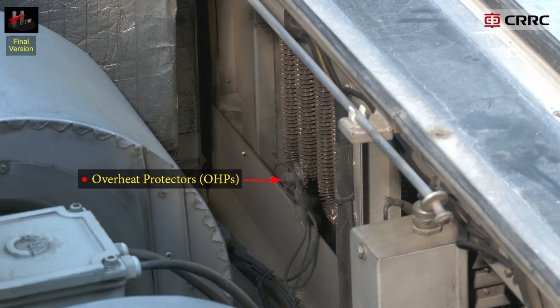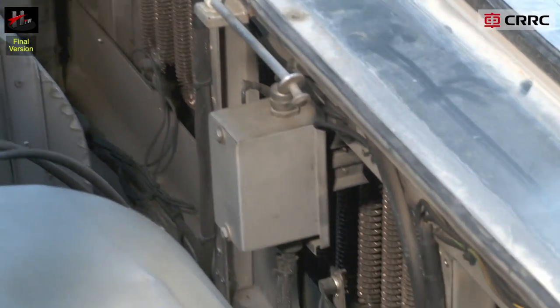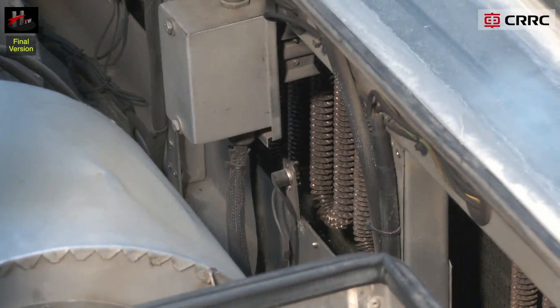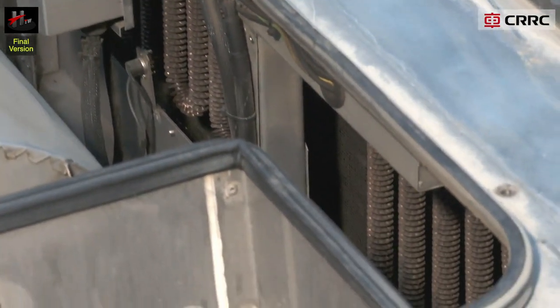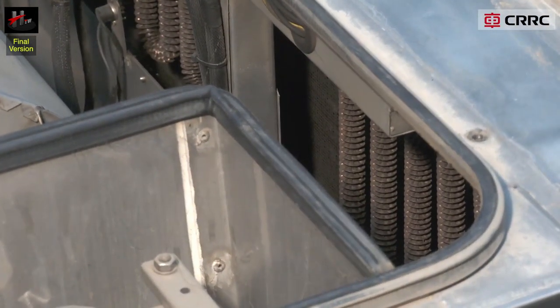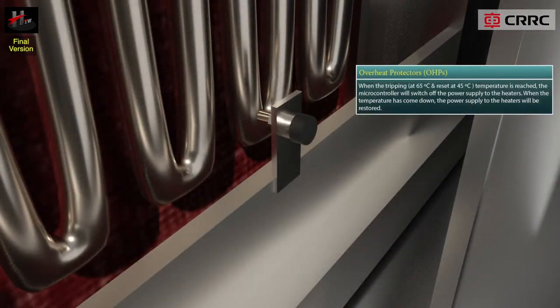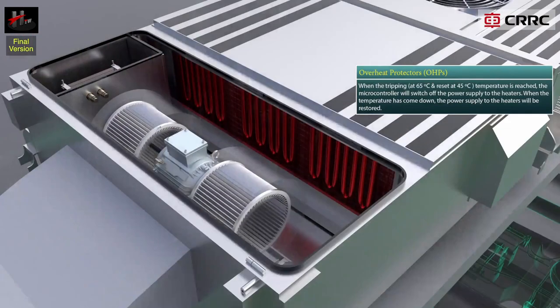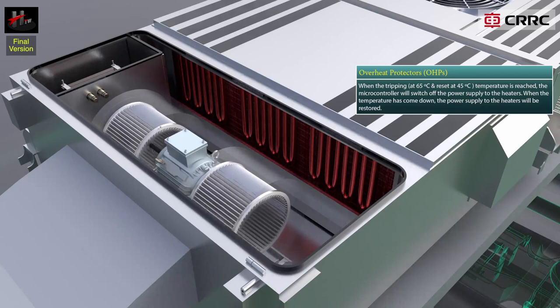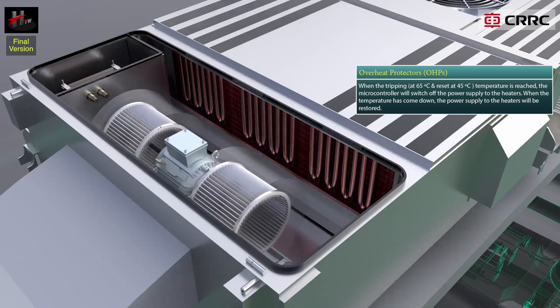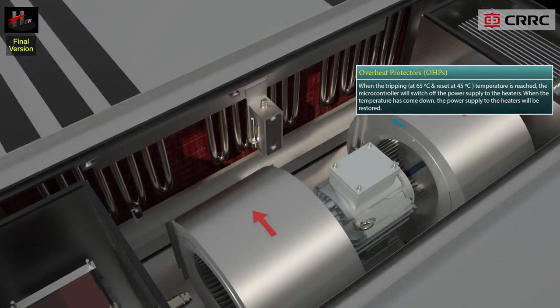The overheat protectors or OHPs are an arrangement of three auto-resetting temperature switches connected in series, installed on the downstream side of the heater bank. When the tripping temperature of 65 degrees centigrade is reached, the microcontroller switches off the power supply to the heaters. When the temperature has come down, the power supply to the heaters will be restored.